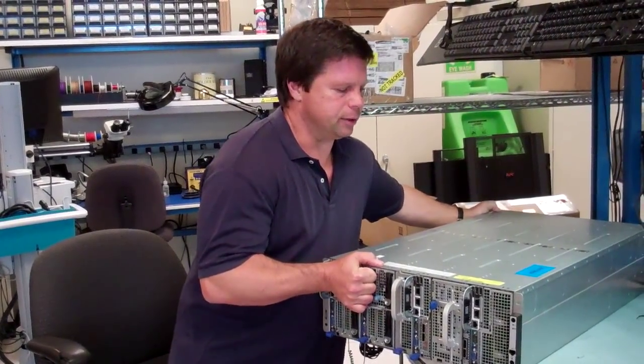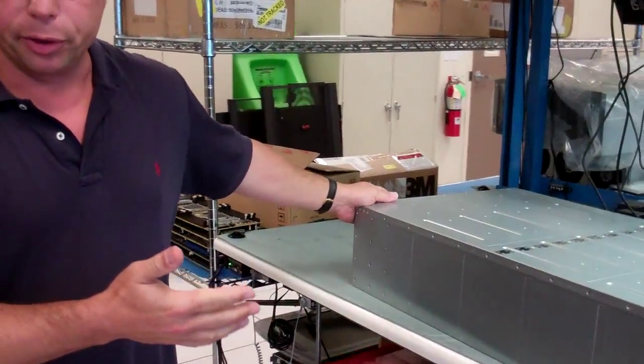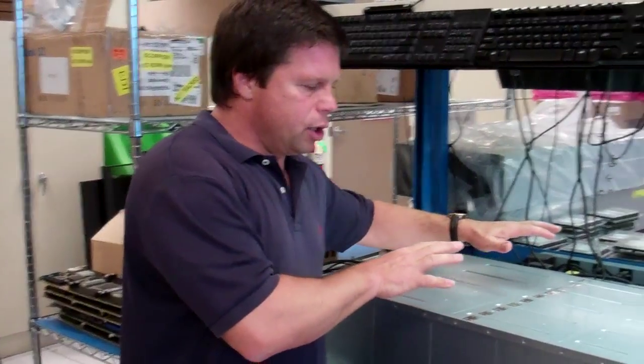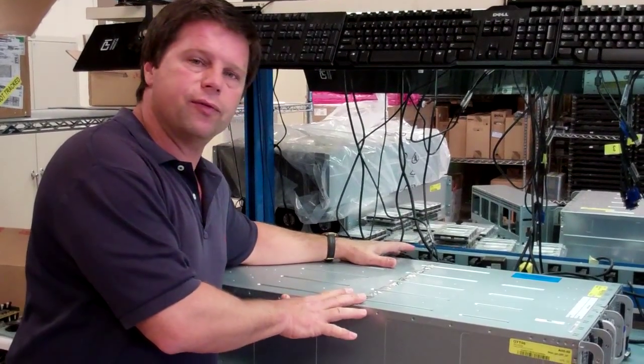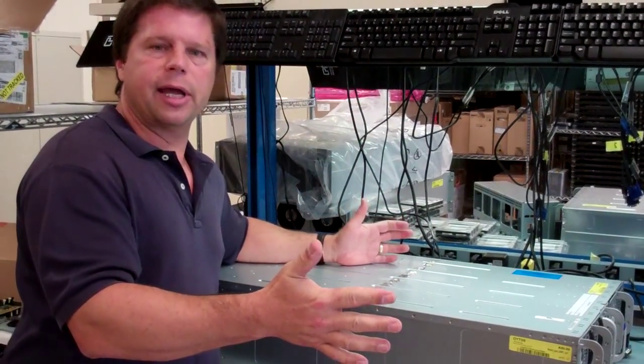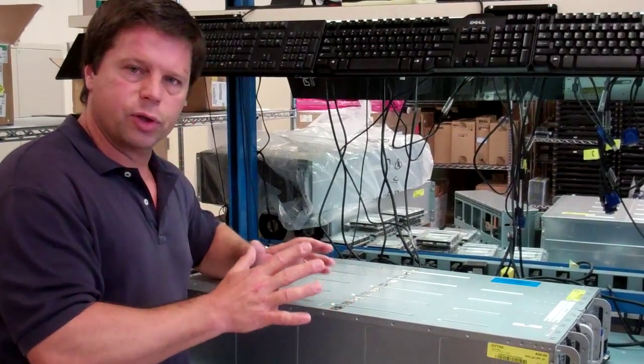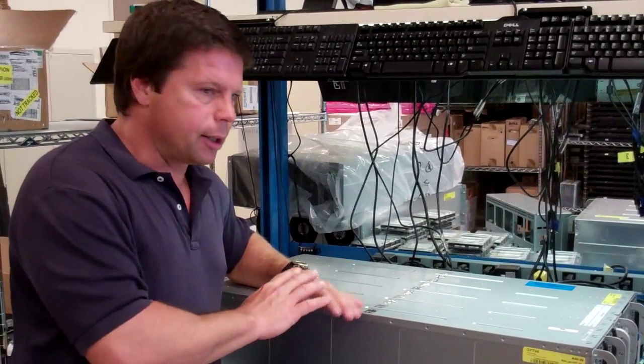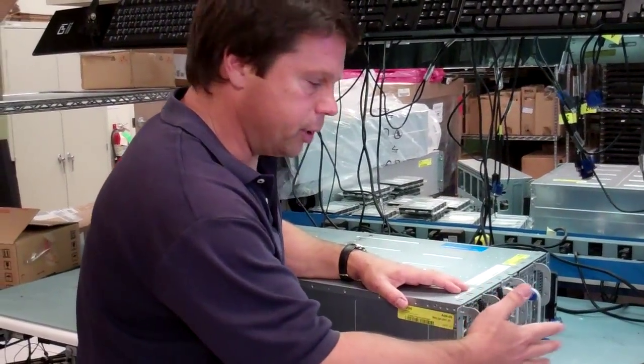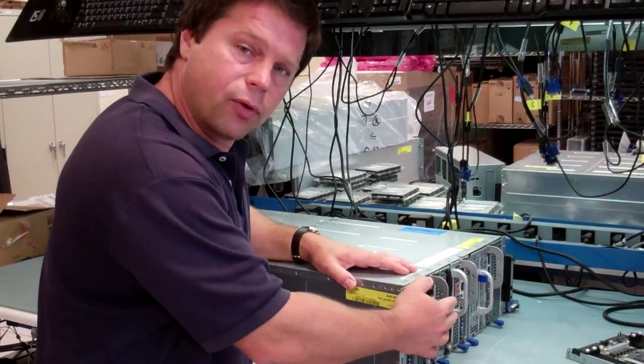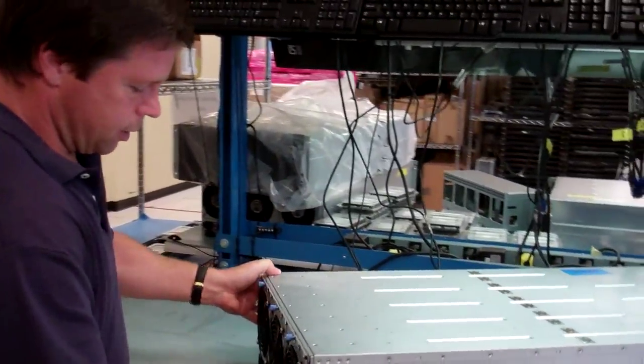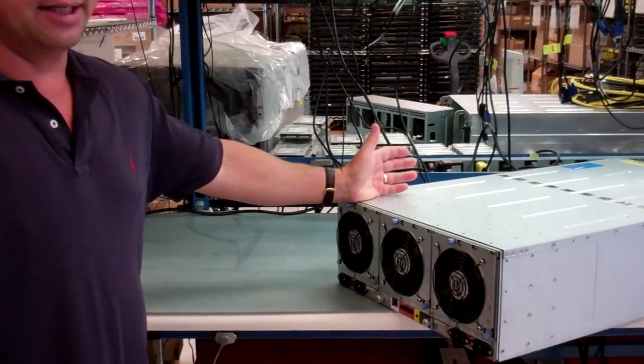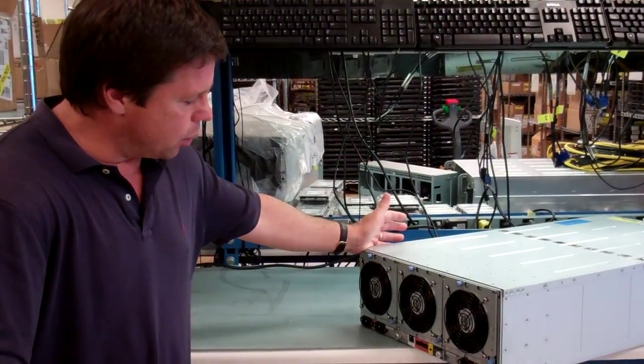Now on the back side, if we turn this around, which is always a task, what we were architecturally going for is we wanted to build a casing that was about as simple and straightforward as taking a chunk of rectangular air conditioning duct. And we wanted that to be extremely passive, something that you could bolt into a rack and never have to remove, and then basically have all of your node and cables and drives and everything else accessed out the front. And then in the rear, very simply, we wanted to have a very minimal need to come back to the hot aisle and service this.